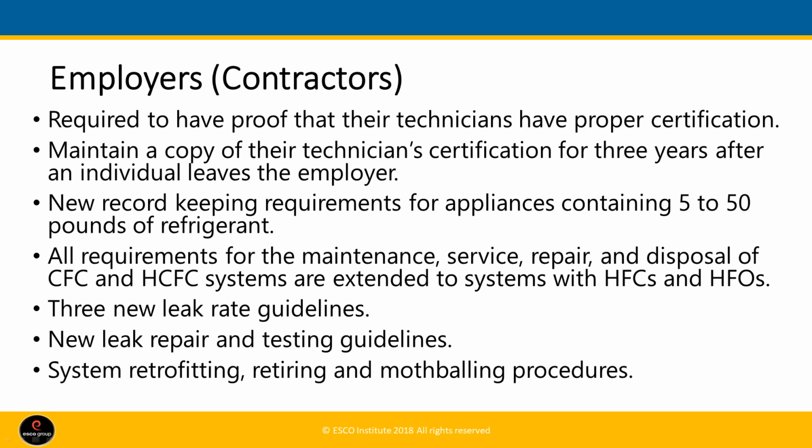Employers must be aware of and adhere to new regulations, as they are now required to have proof that the technicians have the proper certification level for the equipment they're servicing. They must also maintain a copy of the technician certification at their place of business for 3 years, even after the certified technician leaves the employer. They've got to keep the records for 3 years.